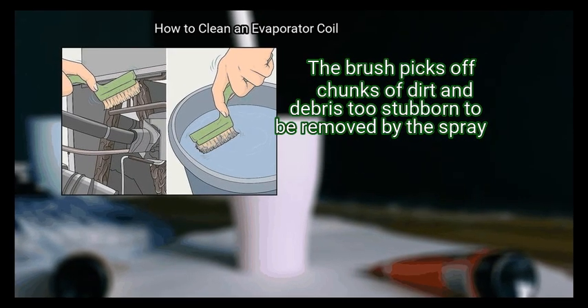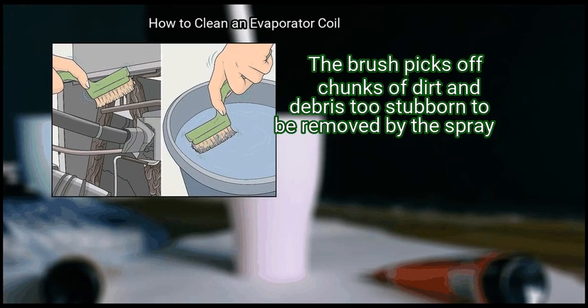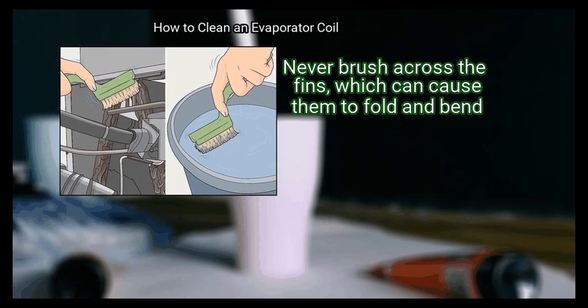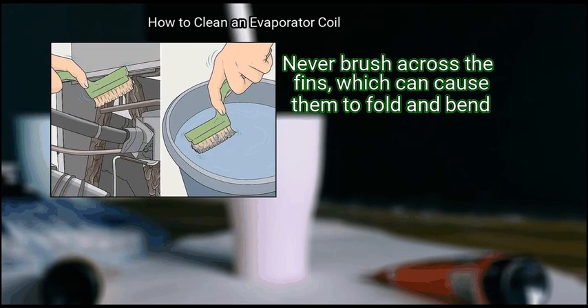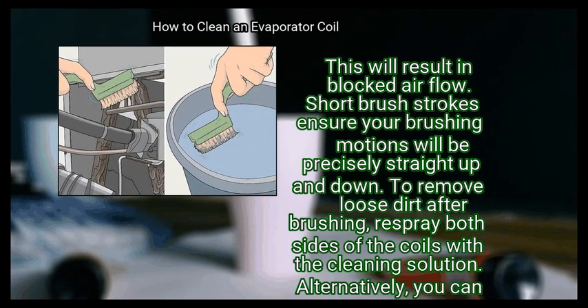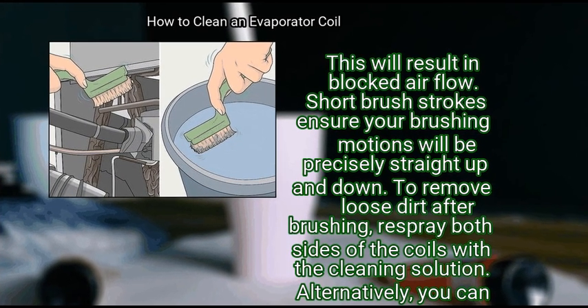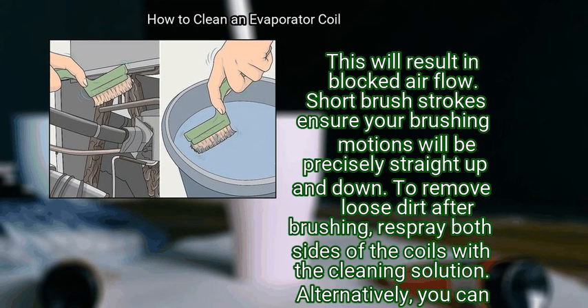The brush picks off chunks of dirt and debris too stubborn to be removed by the spray. Never brush across the fins, which can cause them to fold and bend. This will result in blocked airflow. Short brush strokes ensure your brushing motions will be precisely straight up and down. To remove loose dirt after brushing, respray both sides of the coils with the cleaning solution. Alternatively, you can use the brush attachment on a vacuum to remove and suck up all of the dust.